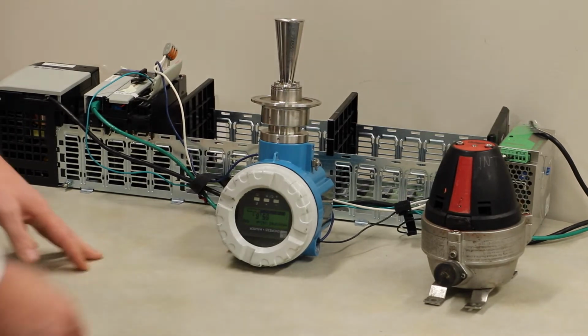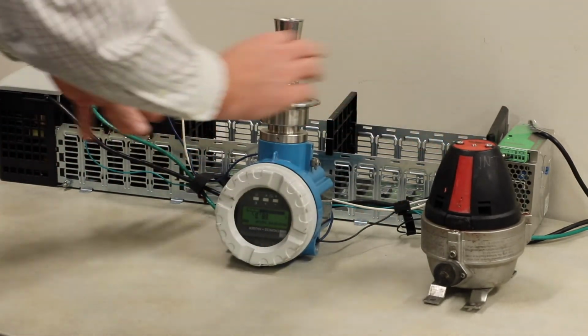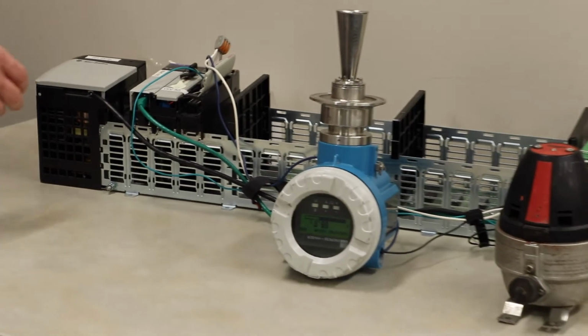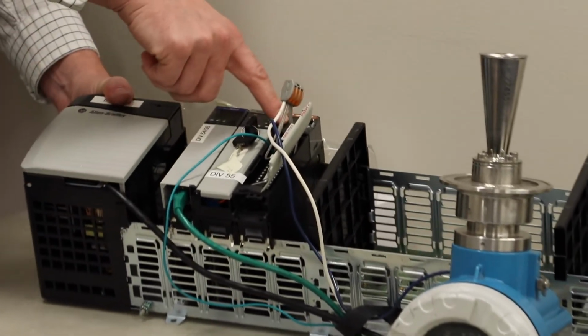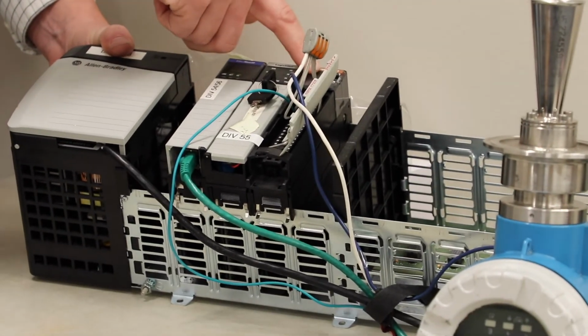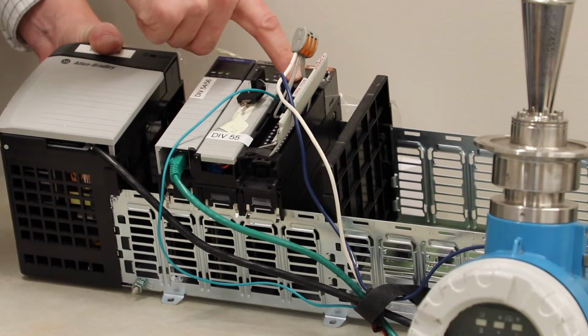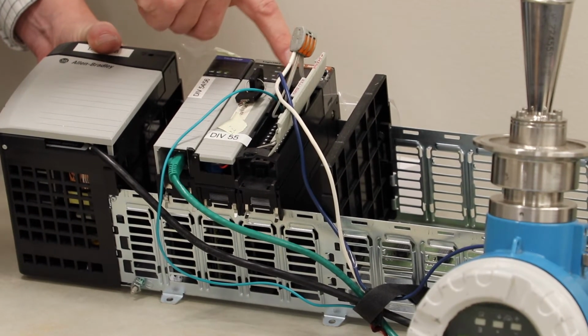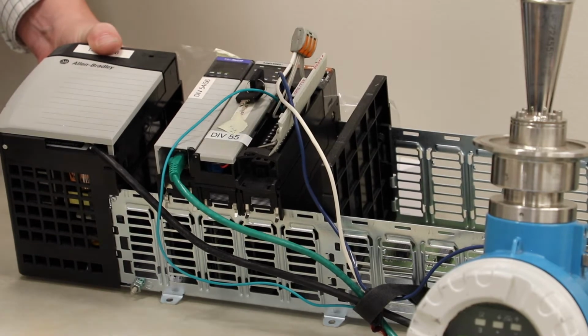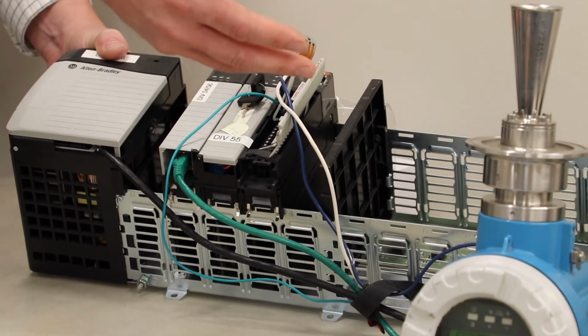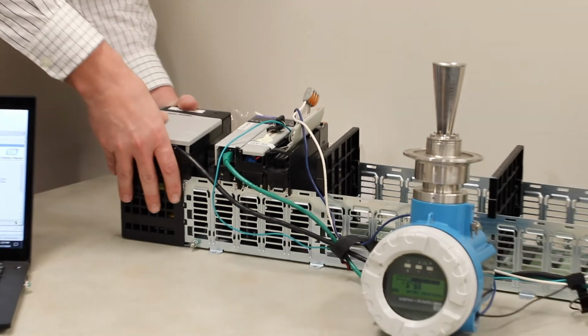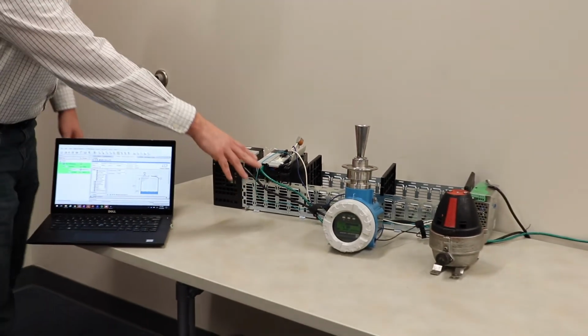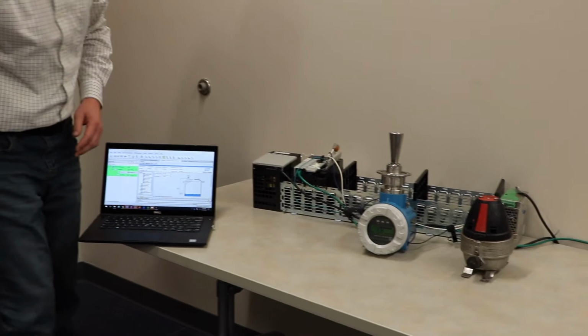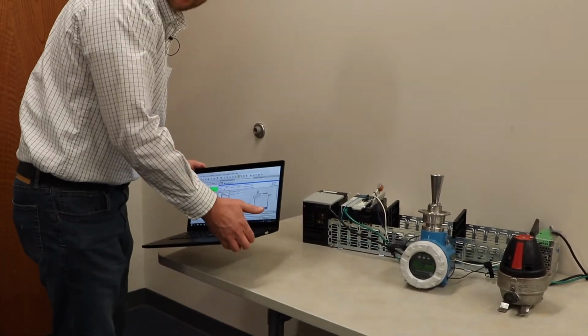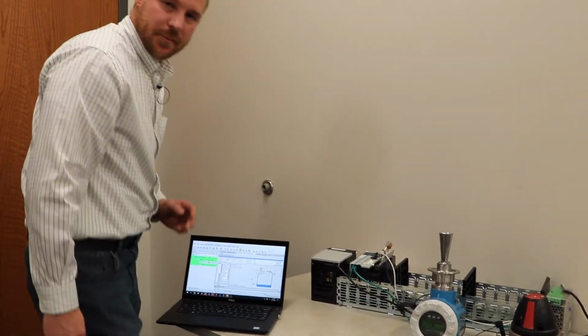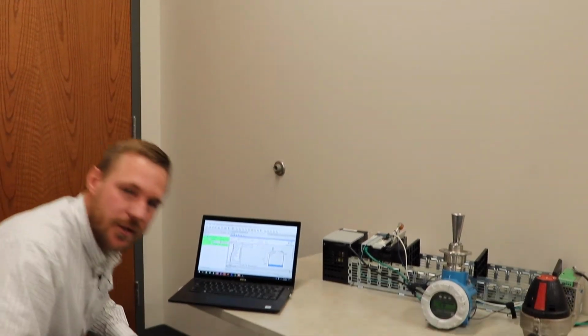So from the instruments, we have our wires coming back to the analog input card, which is in slot 3 here. ControlLogix 1756 input card with HART communication. That's important. It's got to be the HART version of the card in order to pass through the signal from each of the devices into the control system. The control system is then connected via Ethernet cable back to our network. My laptop is then wirelessly connected to our network in order to communicate with the control system.